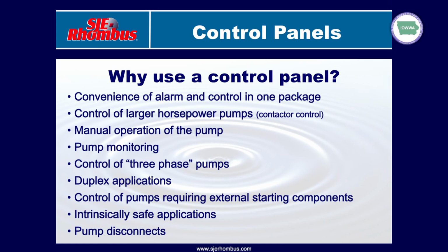All right, we're going to shift here to control panels and talk a little bit about the installation practices that are best designed for the control panel. One of the questions that comes up a lot: we know that we can control a sewage or an effluent pump with a lowly float switch that goes up, turns the pump on, drops down, turns the pump off. So one of the questions a lot of times is trying to convince your customer why they would benefit from having a control panel for their pump as opposed to just a switch.